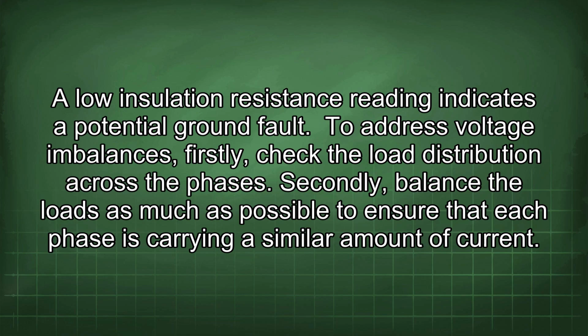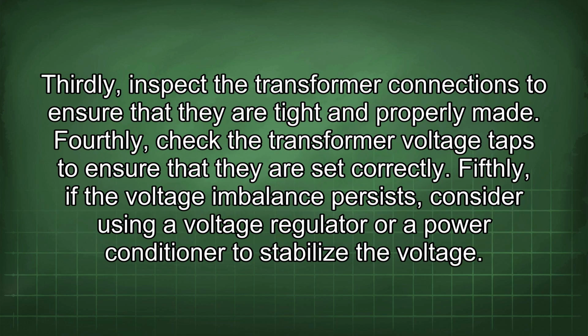To address voltage imbalances, firstly, check the load distribution across the phases. Secondly, balance the loads as much as possible to ensure that each phase is carrying a similar amount of current. Thirdly, inspect the transformer connections to ensure that they are tight and properly made. Fourthly, check the transformer voltage taps to ensure that they are set correctly. Fifthly, if the voltage imbalance persists, consider using a voltage regulator or a power conditioner to stabilize the voltage.